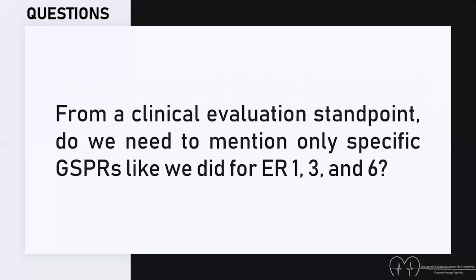Yeah, so I would start by saying that this typically is done from a more holistic approach, where we start from the claims and intended user, and so on, as the basis for what you're writing down. Link that back to the risk, the benefit per claim, per hazard, and so on. That should be the overall goal, to make sure that the risk-benefit is substantiated throughout the documentation. But if you want to be a little bit more specific about which GSPRs really talk about clinical evaluation, I would say there's a few.